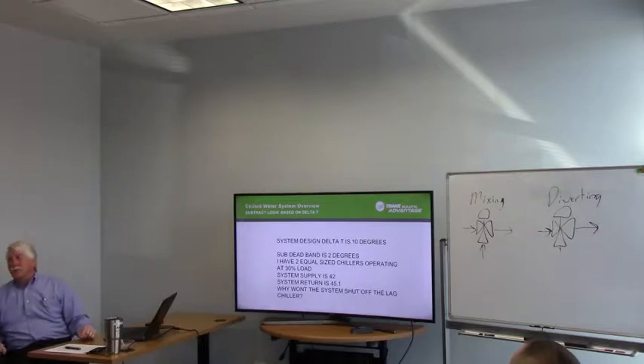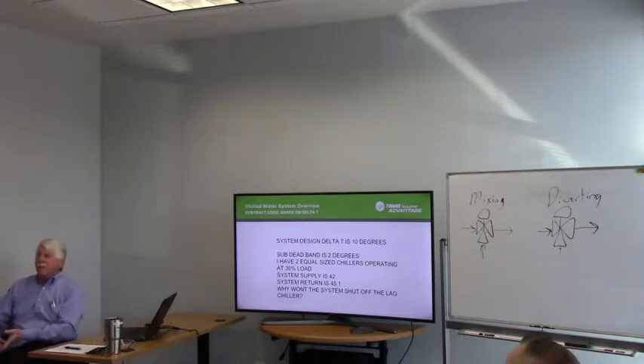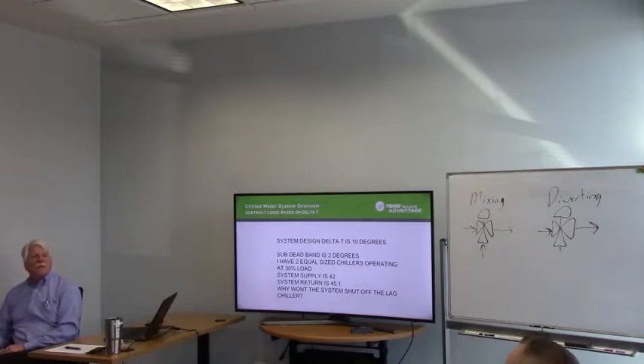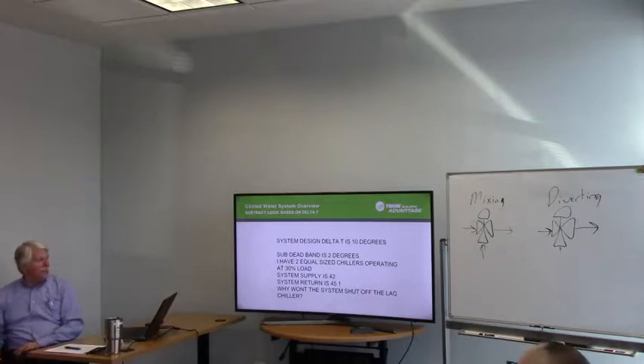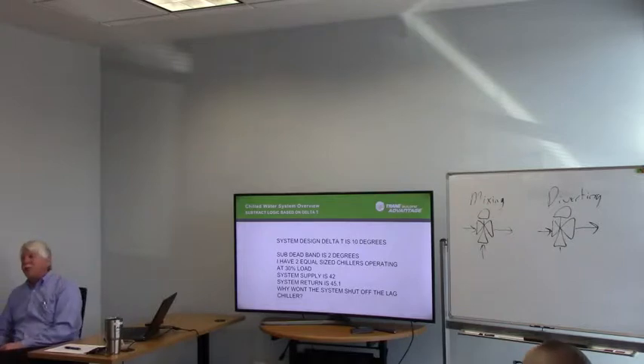And the customer's going, what's the matter with your chiller plant control program? I'm running 2 chillers at 30% load. I don't need that second chiller running. That's not efficient. What do I want to do? Does anybody know why the system won't shut off the lag chiller?